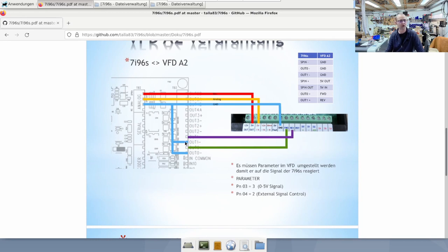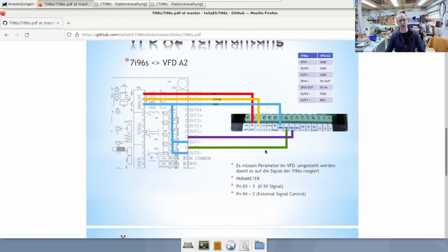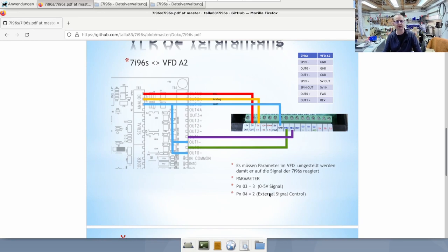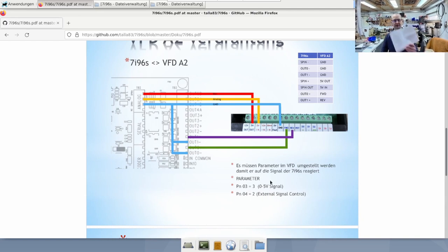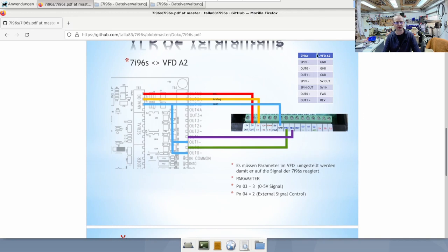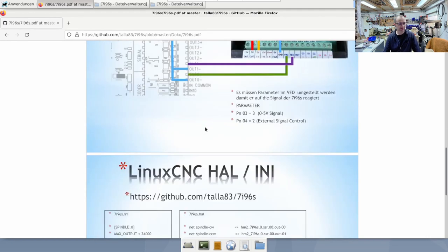As I said, forward, backward I have here with outputs connected so that I can via Linux switch the output and thus influence the direction of rotation, so that the frequency converter does the same. To do this it is necessary to simply set parameters in the frequency converter itself and every frequency converter has its own instruction manual and they should be studied. So my case is shown here again as a table. Important is spin out with 5 volts and the voltage which goes in here in spin plus and minus comes throttled or not throttled out here and makes the speed specification. But we'll see that right away.